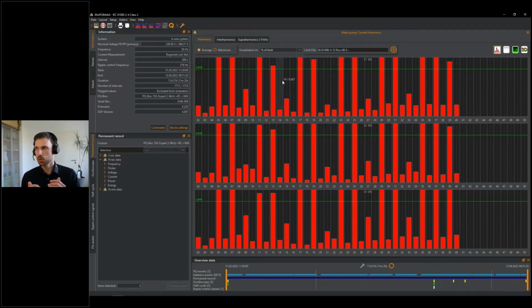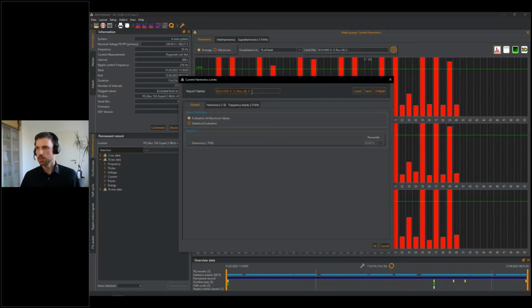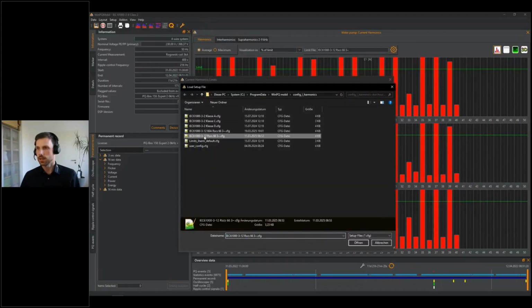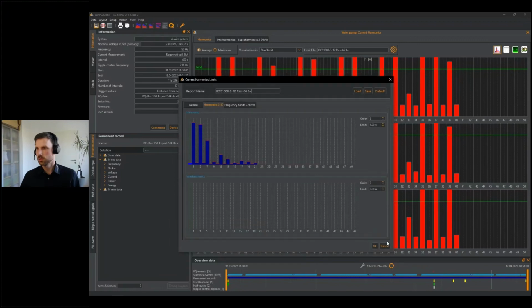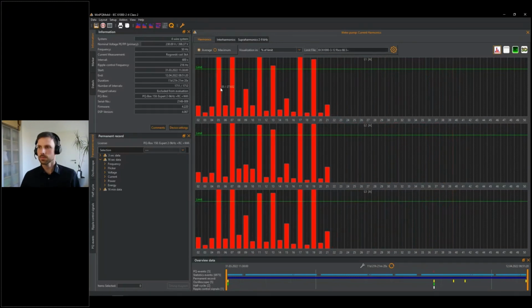So I can figure out which limit values have to be changed to get below the limit lines. I can play around with this as well, and change this as I wish. I can open another standard as well if I want. Go with OK. And now, for example, I only evaluate up to the 21st harmonic. All the others disappeared. So I can do many adjustments within the individual limit values as well as with the limit values from our standards.